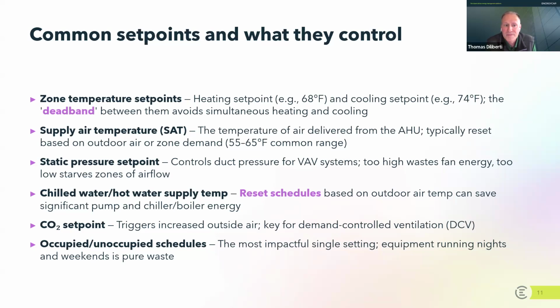The concept, though, of deadband is really important that you understand, and I want to take you through an example so you can appreciate how most systems operate. So let me take you through a day in the north in the wintertime when it's cold outside. A building might be coming off of a setback. So let's just say the inside temperature of a building is 65 degrees. It's 5 o'clock in the morning, the system's turned on and it has to start to heat the building. In this example, the heating set point might be 68 degrees Fahrenheit. And if it is 65 degrees to start, the building will actively and aggressively heat to bring the building up to the set point of 68 degrees.